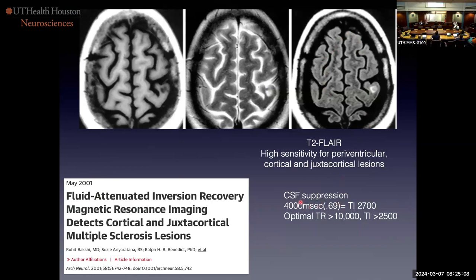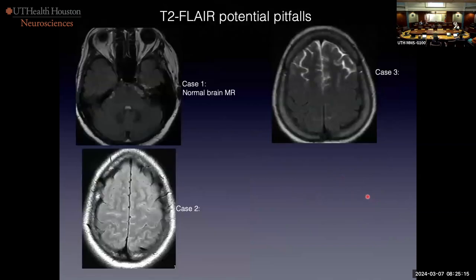The T1 of CSF is four seconds times 0.69, which gives me the TI I want to use ideally. Let's look at some T2 FLAIR pitfalls. The first case is a normal brain MRI. Why does FLAIR fail here? Why do I lose suppression around the brainstem and in the fourth ventricle? The inversion pulse is slice-selective — the slice-select gradient is on, so it only inverts the spins in that slice. So if there's any inflow of unsaturated spins, this is what you're going to get.